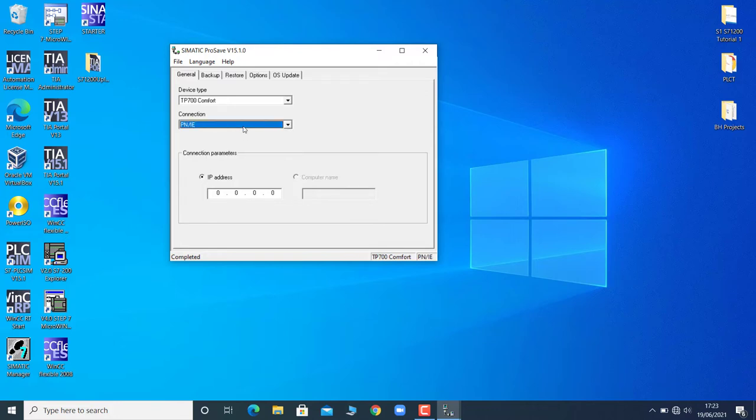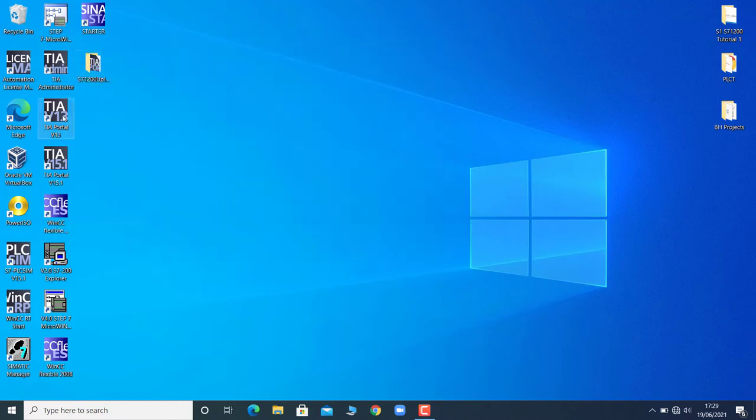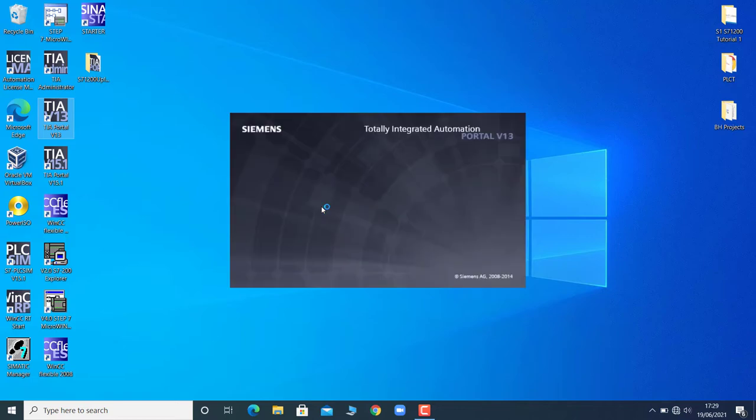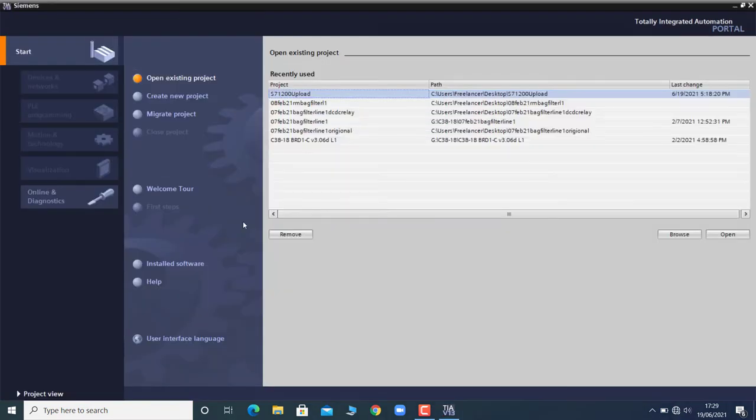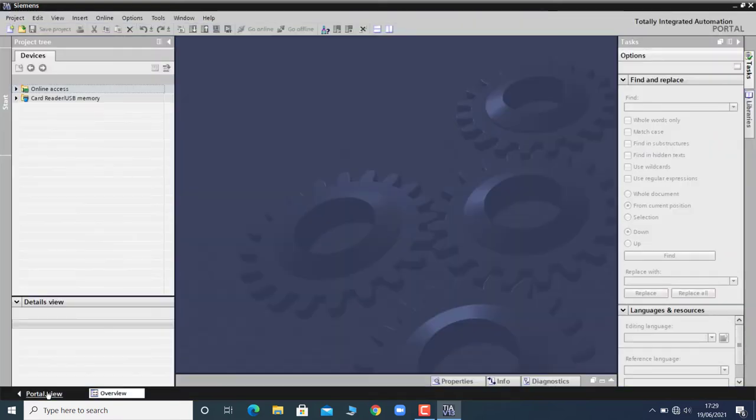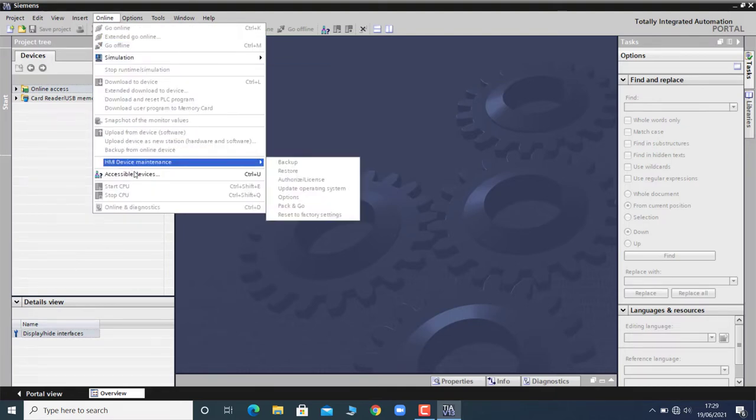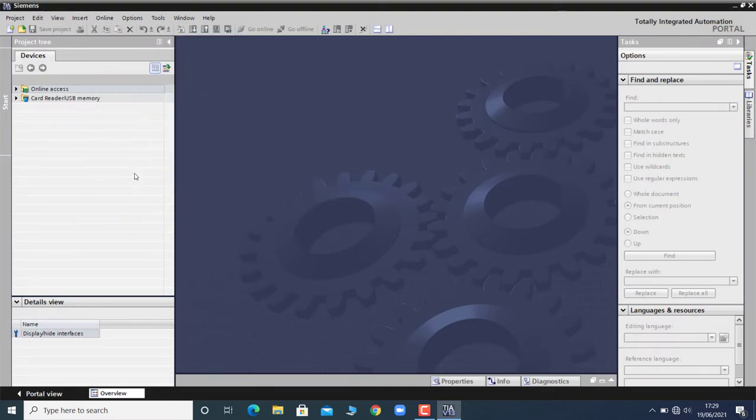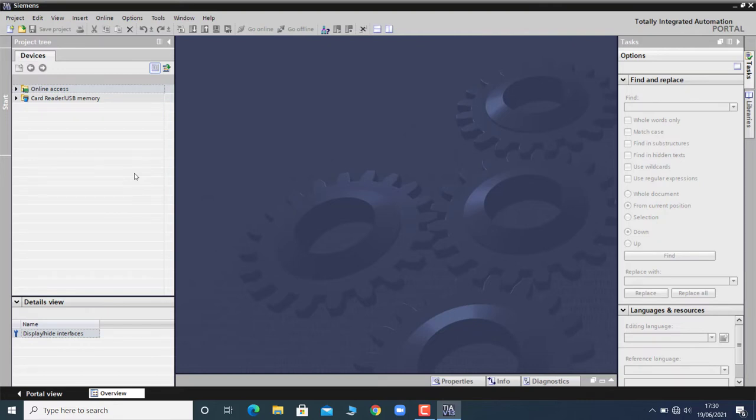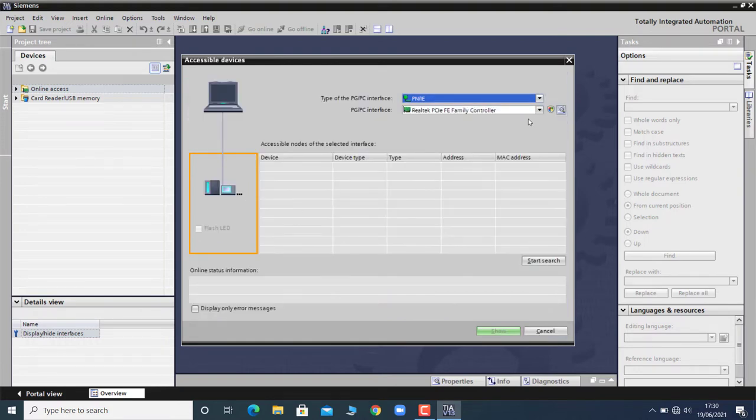Before doing that, since I have connected an ethernet cable, I wish to establish an ethernet connection with the HMI, so I must know about the IP address of the HMI. If I don't know, let me go to the TIA Portal and go to the online accessible devices. It will help me get the IP address of the Simatic HMI. Since my PG is connected to the Simatic HMI, it will definitely establish an ethernet connection and will fetch the IP address.